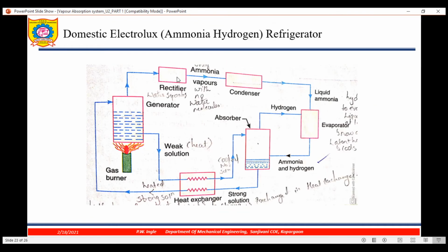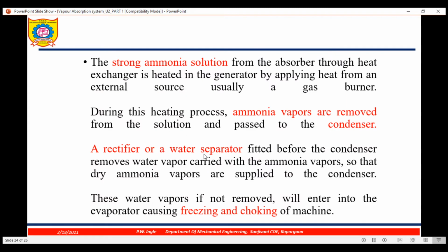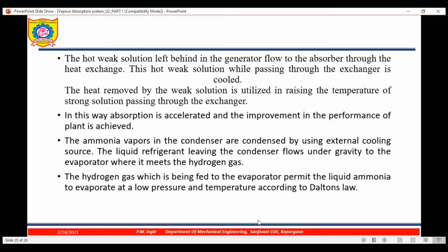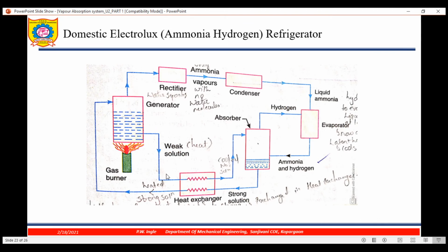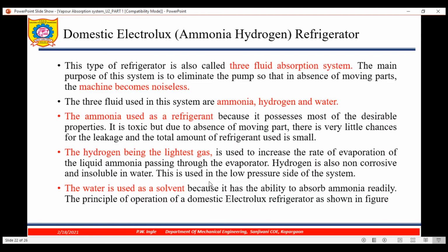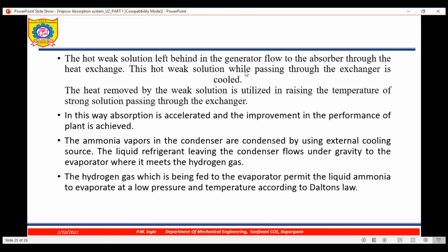So the water separator is used to separate the water vapor which is carried away by the ammonia vapor. Now ammonia is supplied to the condenser. These water vapors, if not removed, will enter the evaporator, causing freezing and choking of the machine. Now the hot weak solution which is left behind in the generator.